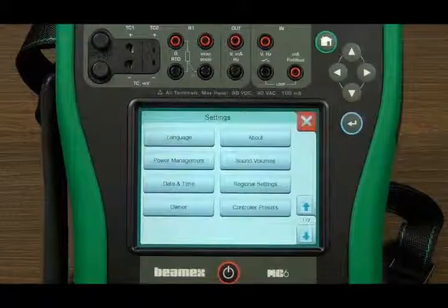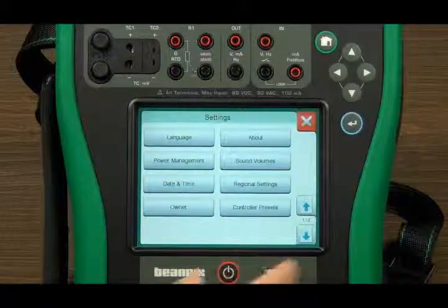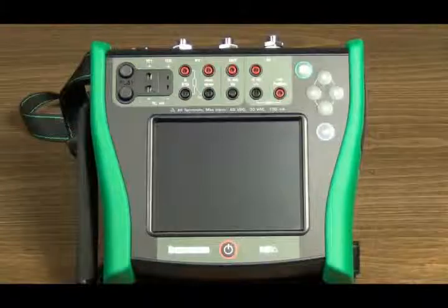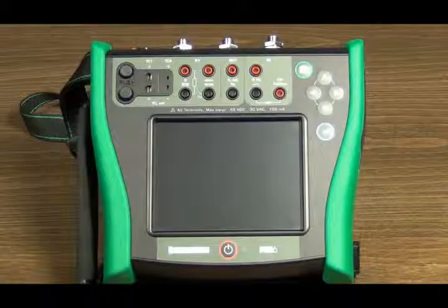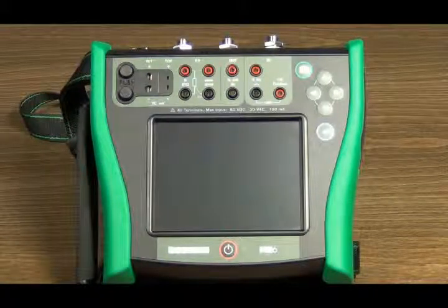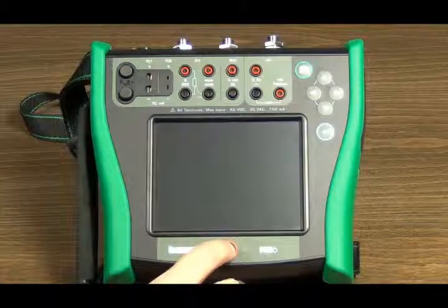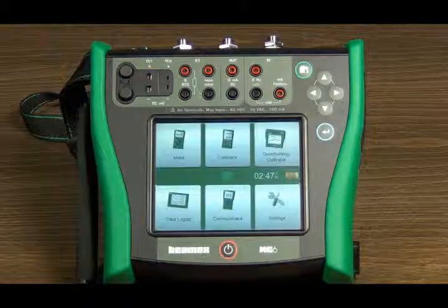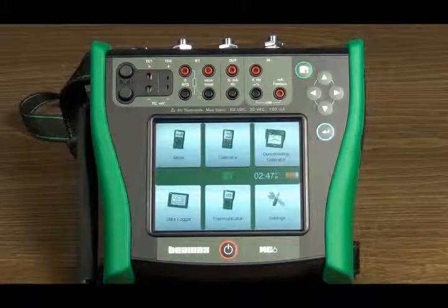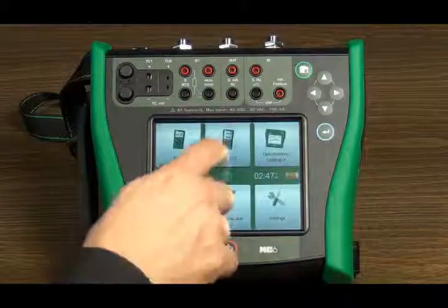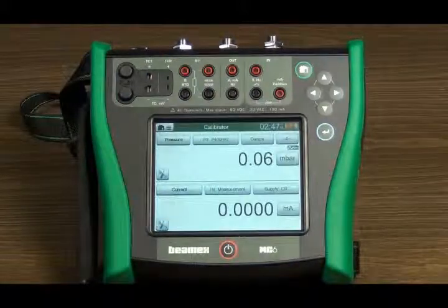Settings. The settings allows you to edit the various settings of the calibrator. The calibrator mode is designed for testing and calibrating various process instruments. It enables 2 simultaneous measurements, or generation and measurement. Touch the calibrator icon in home view to open the calibrator mode.